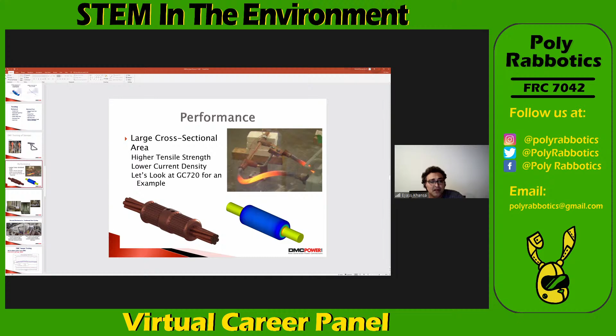In this test we run 85 kiloamperes and then make sure the fitting will not fail. At very high amperage, you see the cable glowing red, about to fail or melt, so we have to withstand that. You have to have a good cross section and a good connection. So this is one of the tests to make sure that you are good.